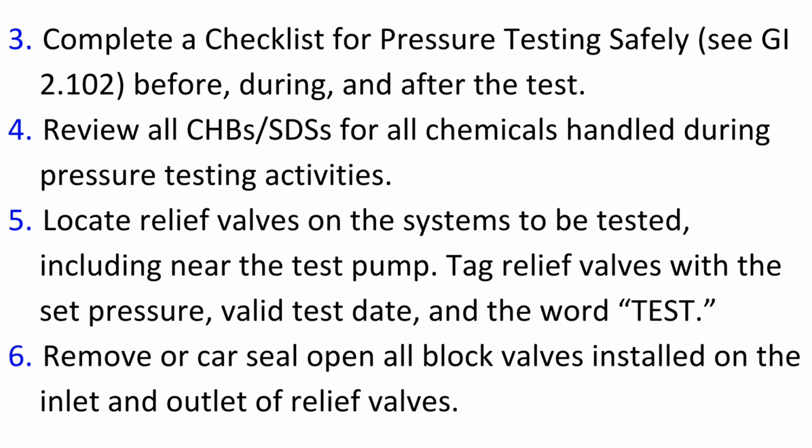4. Review all CHBs and SDSs for all chemicals handled during pressure testing activities. 5. Locate relief valves on the systems to be tested, including near the test pump. Tag relief valves with the set pressure, valid test date, and the word test. 6. Remove or car seal open all block valves installed on the inlet and outlet of relief valves.